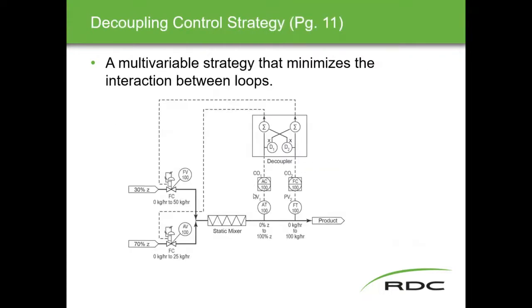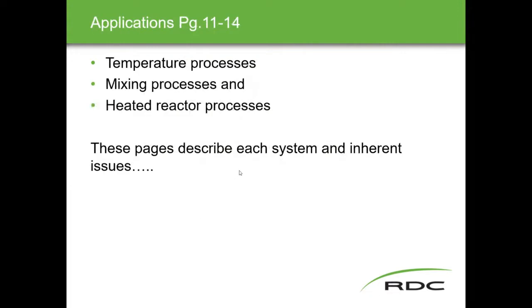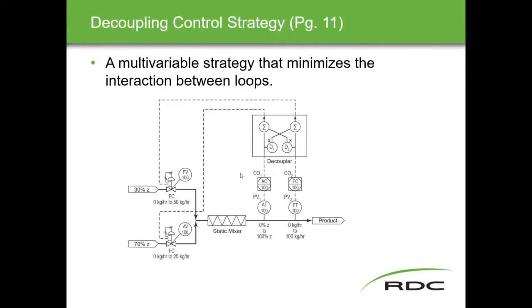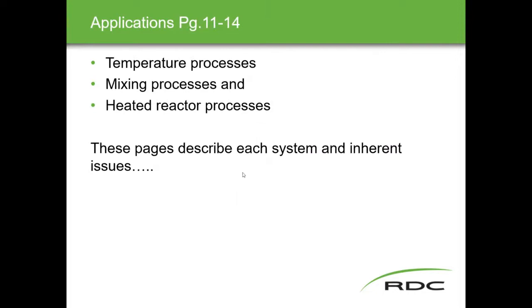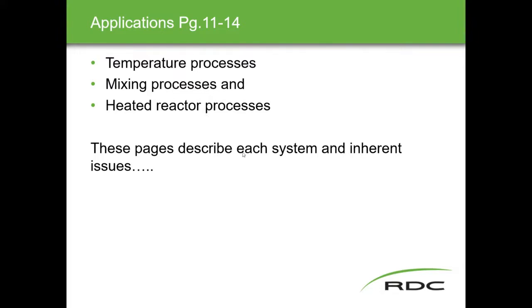That leads us into decoupling control strategy. We know what the interaction is between the two — one affects the other by a factor of three, and one affects it by one. There's math we can use to calculate values to put in here to minimize the effect of one change on the other loop. Common applications for decoupling include temperature processes, mixing processes, and reactor processes — pages 11 to 14.